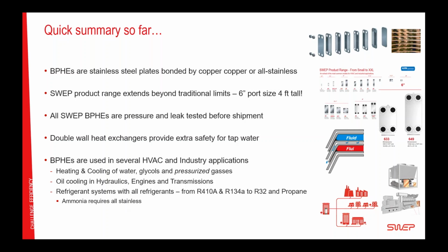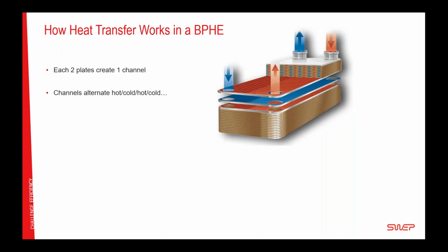I will move on. So let's go a little bit deeper inside how heat transfer works in the brazed plate. Every two plates create one channel. So for each two plates, you get another heat transfer channel, and by adding more and more plates, you get the hot side, the cold side, the hot side, the cold side, the hot side, the cold side, etc. So the hot and cold side, when it goes in, will have a lot of surface contact with each other all along these alternating channels, and that is what makes the heat transfer so efficient, together with the turbulence inside. We will look at that.